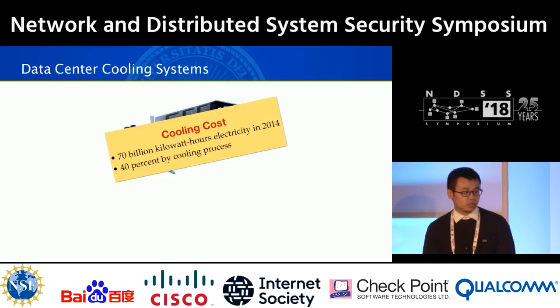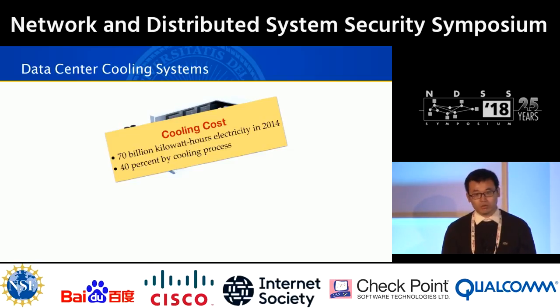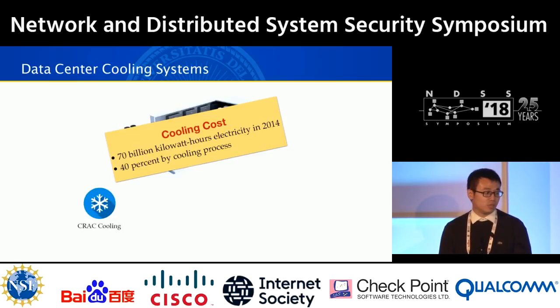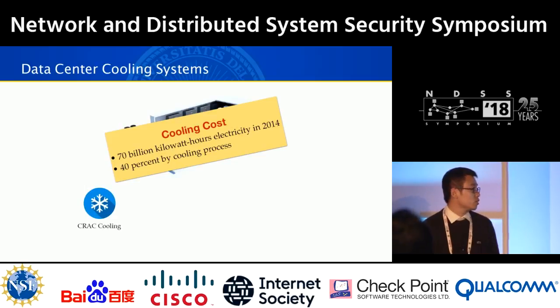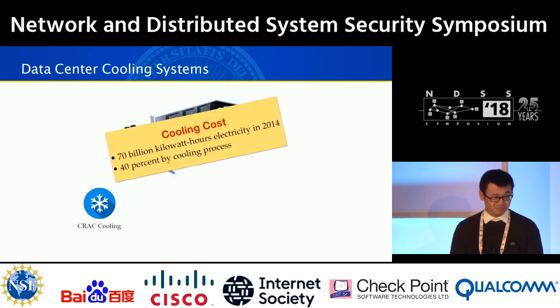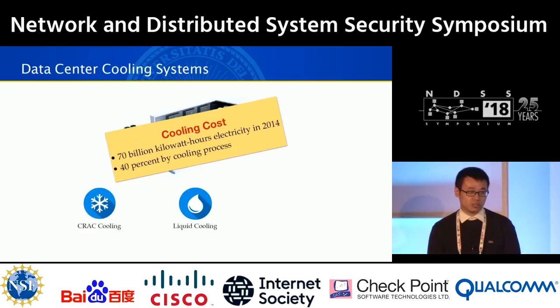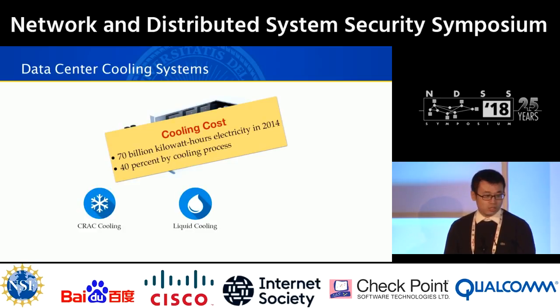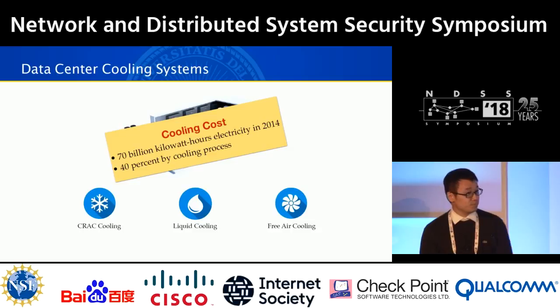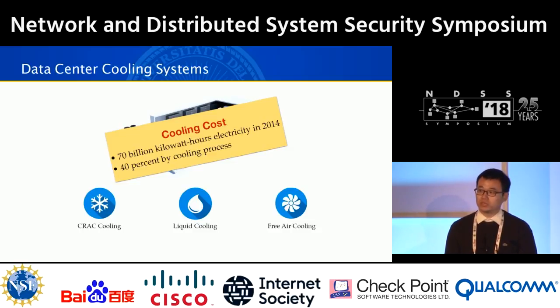To cool down servers, today's data centers are equipped with several different technologies. For example, the CRAC cooling system, the traditional computer room air conditioner system, relies on a chiller and a cooling tower to provide coolant to absorb heat from the air. The liquid cooling method uses liquid-based coolant, like water, to directly absorb heat from the microprocessor. Also, some data centers are built in colder environments so they can utilize free air to cool down servers.